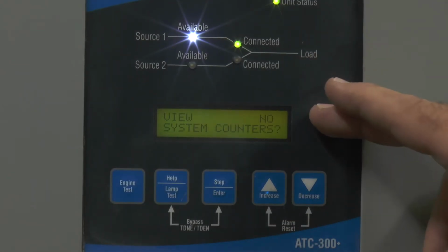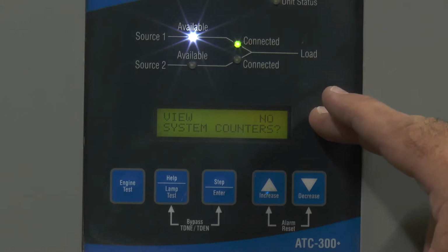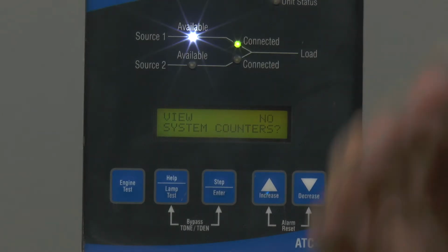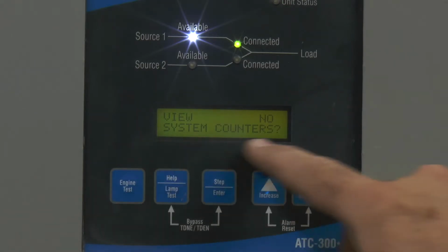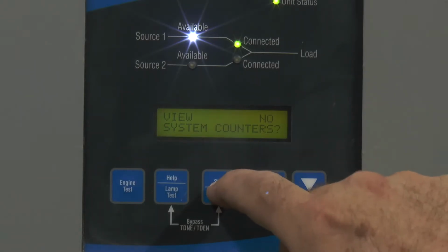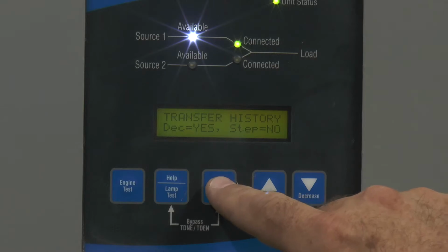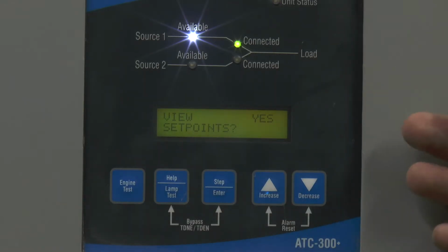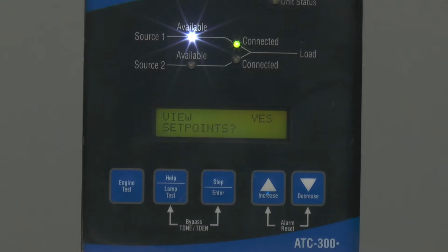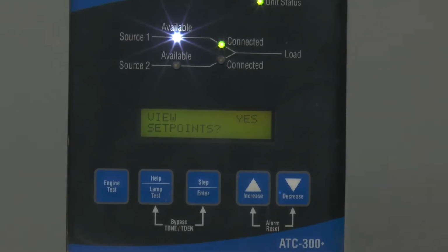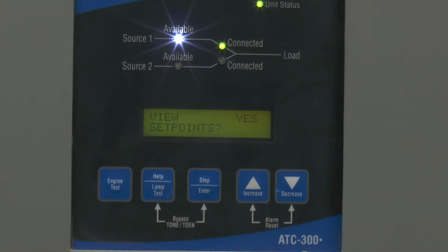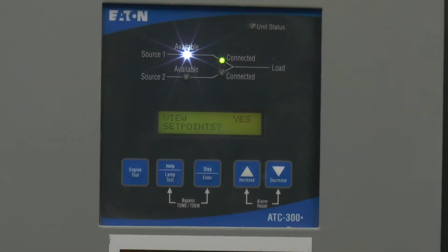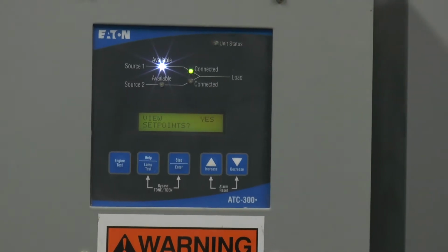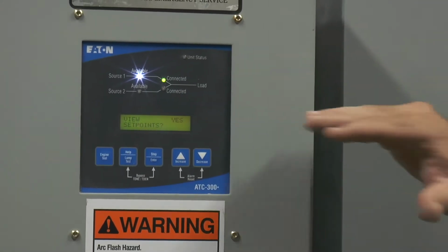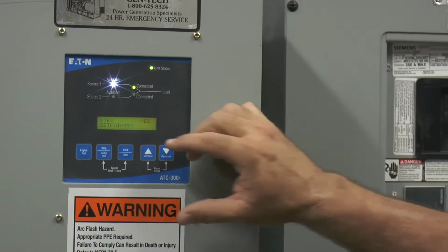All the displays that are picked up here are also going to be available in the fire command room. You just have to go through the HMI display. View system counters, no. Transfer history tells me exactly what caused it. So if you have multiple outages and you get nuisance starting at the generator set, is it a utility issue or is it a load issue? This will tell you if it's a utility issue, if you're losing phase A, phase B, or phase C, or if you're losing frequency. We monitor that here.